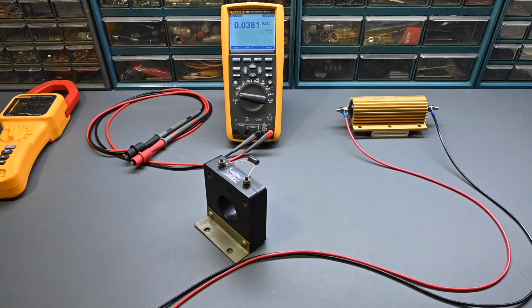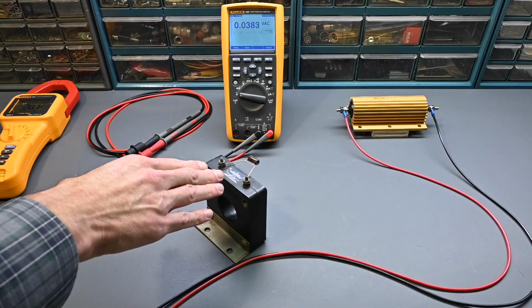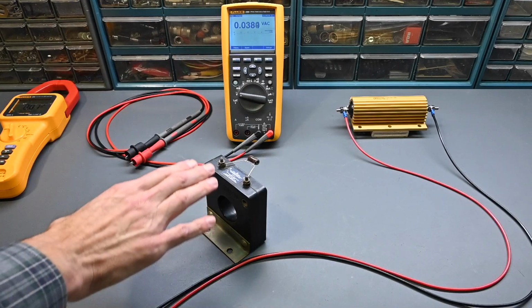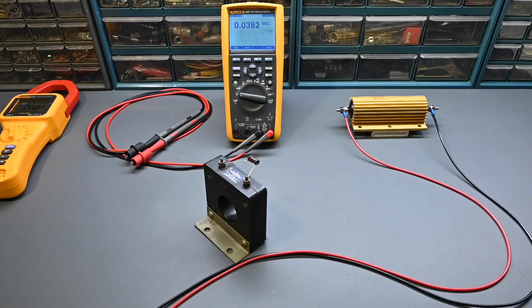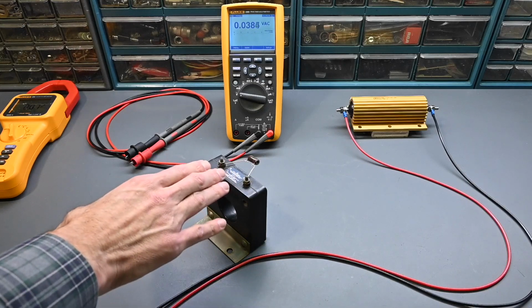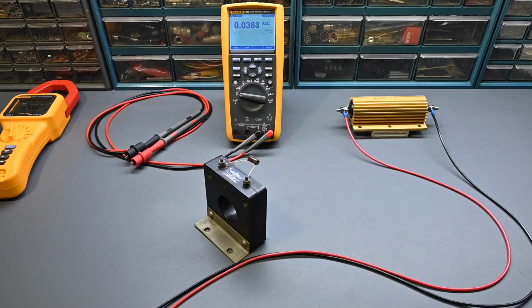They're often used in the instrumentation for power generators and situations like that, where you have permanent wiring and this is panel mounted or chassis mounted. So current transformers offer very good accuracy, and they can measure extremely low current up to very high current depending on the turns ratio. But of course that accuracy is going to depend on the external meter that you use. So for this example, I'll just measure the voltage that this transformer produces with this Fluke 289, but this could be driving an external panel mounted meter or something like that. And if it's used with an analog meter, then the entire setup can be made passive, because the analog meter can derive its voltage off of this current transformer. It requires no other source of power.